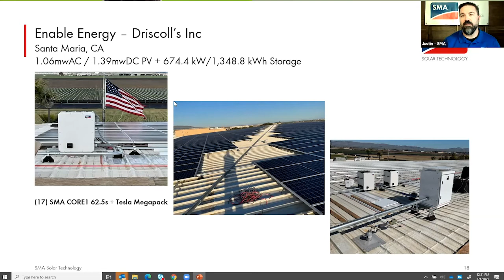One thing that's really nice on this one: you run into a lot of folks trying to do commercial storage, and right now the real usable units out there are AC coupled, like Tesla and a few others. SMA products really do pair well with these other systems. I've seen other solutions try to use an AC coupled battery that doesn't integrate as well, sometimes the inverters just don't play nice with them. SMA does play well. We have a lot of control with our system, especially using our Data Manager, which replaced the cluster controller and does a lot more than just aggregate data into production—things like zero export, limit export, and more. So it plays really well with other systems.